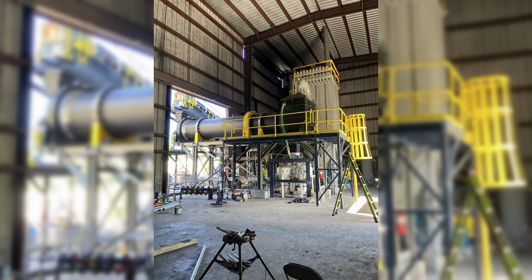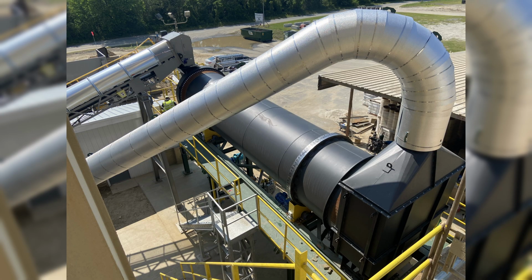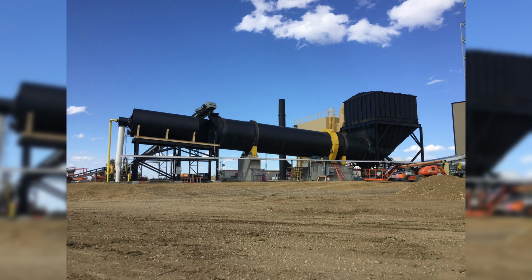You may be drying, you may not be drying, but if you don't have a draft and you're not pulling that heat from the burner through the sand or the asphalt or whatever you've got in your dryer, then you might be hitting production, you might not be, but you're at least wasting some energy because you get blowback. I don't know if we've had customers that have lost draft or not had good control, and you'll melt ignition wires, you'll melt anything back there that's open that can see any of that. The flame will kick back, it'll come out the seals. It can cause problems, especially when you've got a long flame or a big burner on there. And that's the typical thing we see.